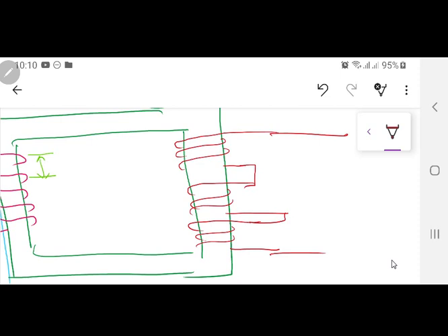And secondly, a very important thing: if there is a discharge and your winding has gone faulty, your transformer could not withstand the 95 kV impulse, what will happen? The winding will be damaged. Which portion of the winding will be damaged? Certainly the topmost one, because it's the first one. Right here the impulse came first. So it's easy to actually repair it all. So we bifurcate the whole high voltage winding into different coils. These are coils. This is going to be called the first coil, second coil, third coil.